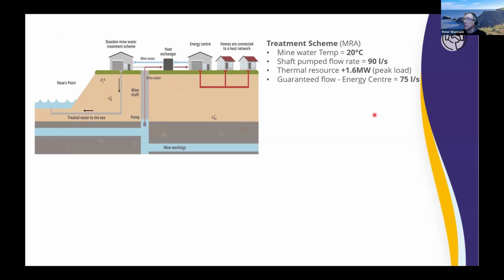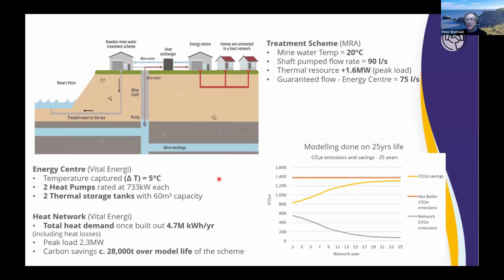So the treatment scheme provides mine water at 20 degrees and a pumped flow rate of 90 litres a second. That gives a thermal resource of in excess of 1.6 megawatts peak load, and will provide a guaranteed flow of 75 litres per second to the energy centre. The energy centre is run by Vital Energi, and they'll capture 5 degrees temperature from the mine water and utilise 2 heat pumps rated at 733 kilowatts each, in combination with 2 thermal storage tanks.